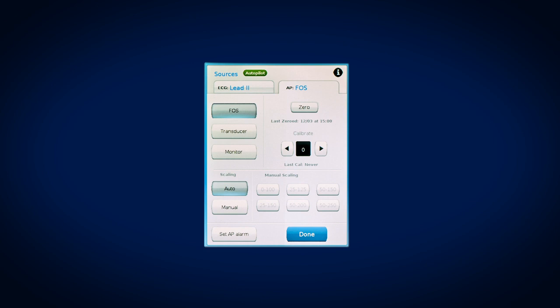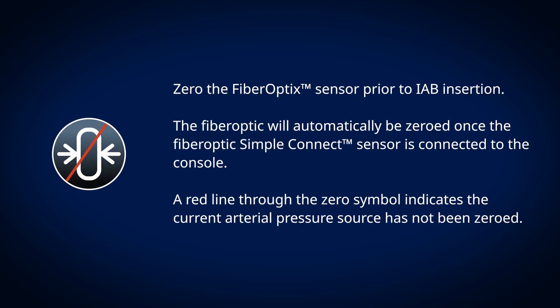The fiber optic will automatically be zeroed once the fiber optic Simple Connect sensor is connected to the console. If the fiber optic sensor has not been zeroed prior to insertion but has been calibrated, the 0 symbol will continue to have a red line through it, and the calibration factor will be displayed below the 0 symbol.